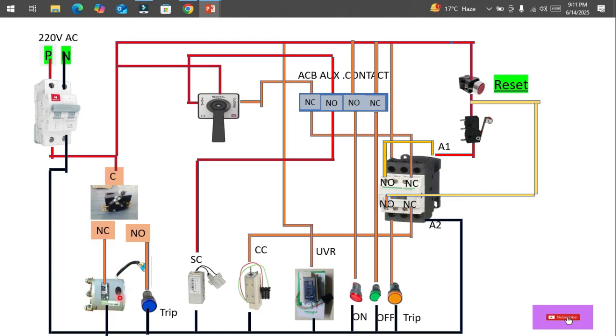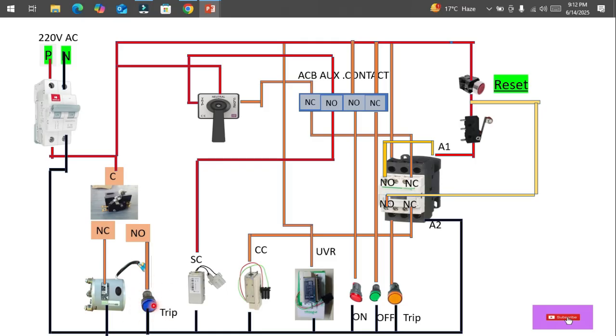Initially when the spring is not charged, power comes through the common point and through the NC contact, running the motor. Once the spring is charged, the micro switch or limit switch gets activated — it is pushed, and the NC contact becomes NO, meaning power is disconnected and the motor switches off. At the same time, the NO contact becomes NC, so power shifts to the spring-charged indicator, which glows to show the spring is fully charged.